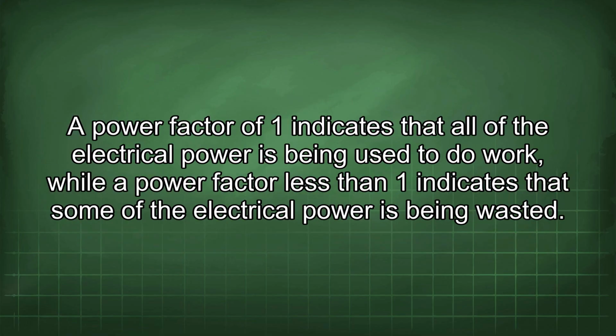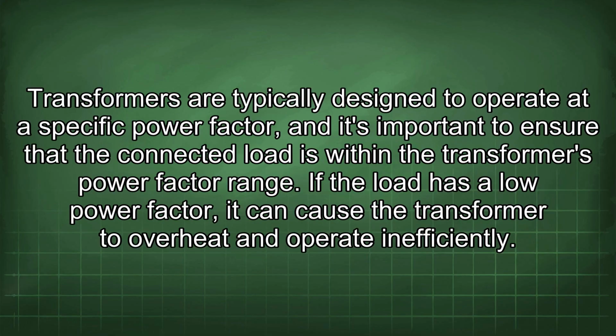A power factor of 1 indicates that all of the electrical power is being used to do work, while a power factor less than 1 indicates that some of the electrical power is being wasted. Transformers are typically designed to operate at a specific power factor, and it's important to ensure that the connected load is within the transformer's power factor range. If the load has a low power factor, it can cause the transformer to overheat and operate inefficiently.